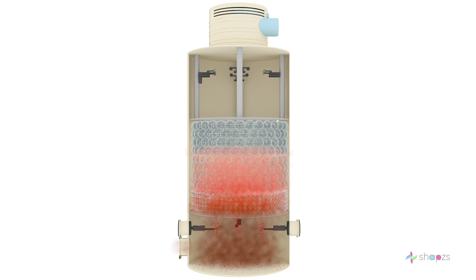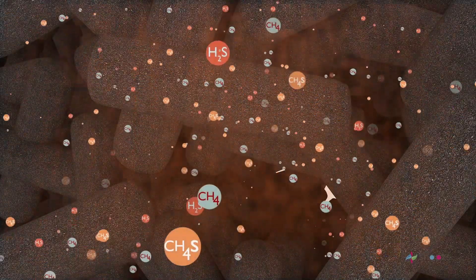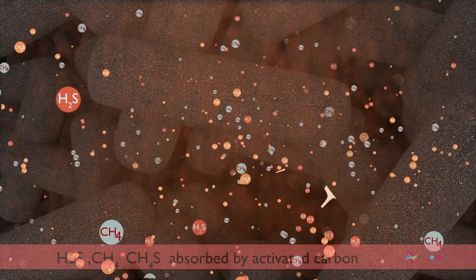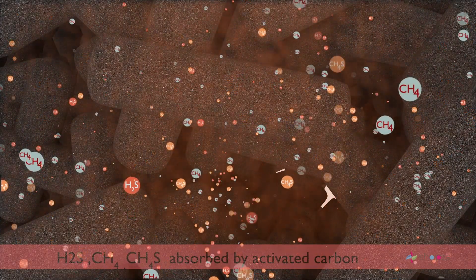The gas removed of H2S then enters the upper layer which has cage balls filled with activated carbon. In this layer the remaining H2S, methane, and mercaptans are absorbed by the activated carbon. The height of this layer will be about 500 mm.